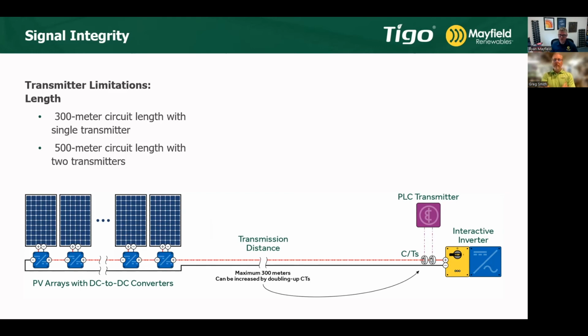Curiosity, Greg, what if I'm more than 500 meters of circuit length? It's like anything that doesn't get the signal, it's just like an electrical network. If somebody's way at the end of a line, they're the ones suffering the voltage drop, and they're the ones whose appliances wear out in 5 years or so. Same thing here. If you go past the 500 meters round trip distance with 2 CTs, the things way at the end will start behaving erratically. It could be they just don't work right some of the time, or something really bad happens and you have to send somebody out to replace everything.